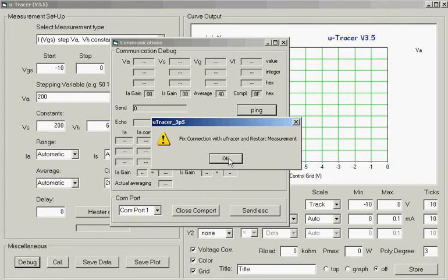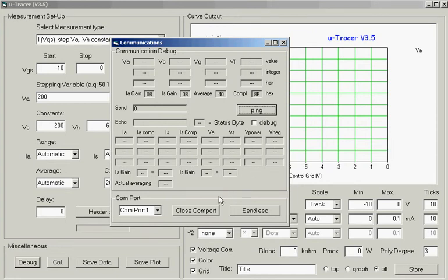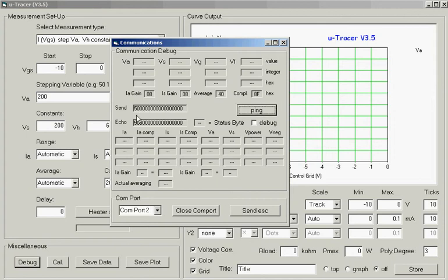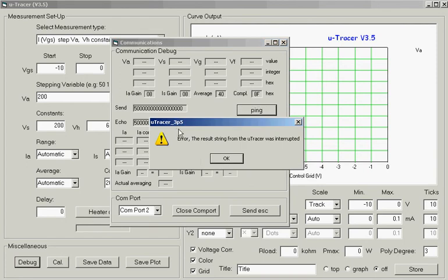So when you see this happening, you are already 99% sure that everything is functioning perfectly. If you also have the emulator circuit, the RS232 circuit which connects pins 2 and 3, connected like I have on port 2, what you will then see when you give the command is that it sends two command strings, a 0,0 string and a 5,0 string, and that these strings are echoed. And when you see these strings echoed, you're sure that all the communication, both the user interface as well as the communication, functioned perfectly.